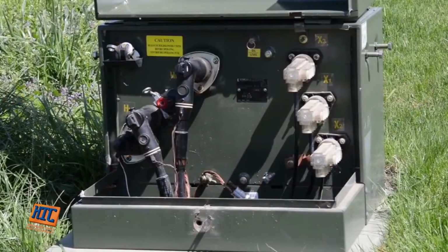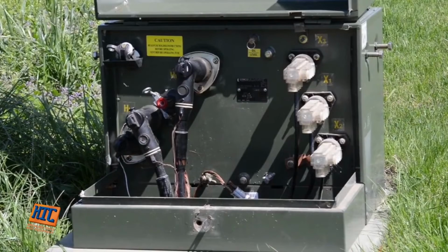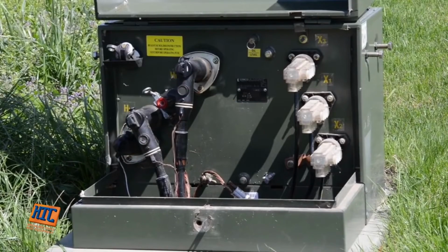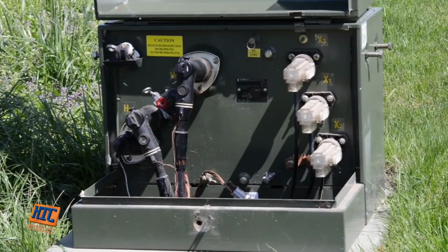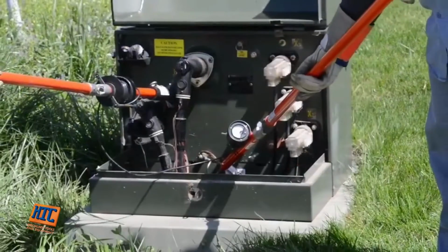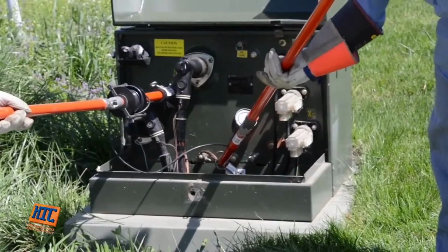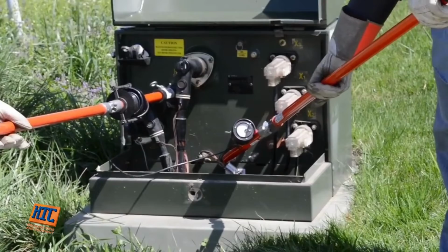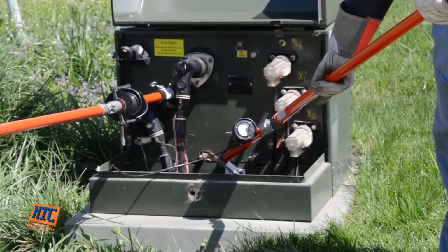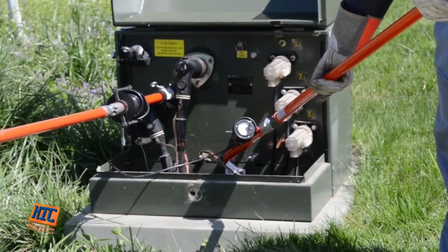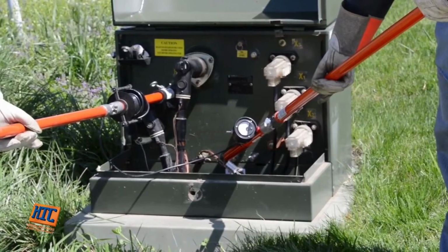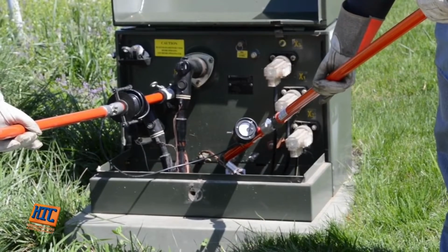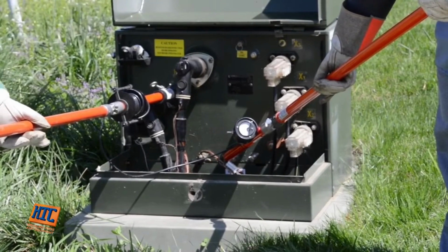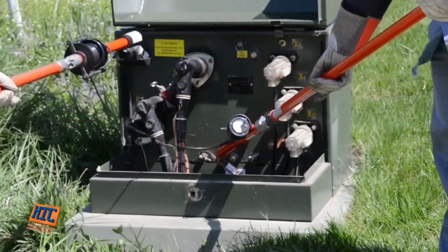Here, notice that a 200 amp load break elbow already has been pulled and parked on a feed-through bushing, and the primary bushing has been covered, all with hot sticks. For this use, the analog phasing tester's reel stick has been fitted with a bushing adapter. Simply insert the probe of the adapter into the feed-through bushing. With the meter stick probe, contact is made with the system ground and the meter is checked for deflection. If there's no voltage present on the cable, the meter reads 0.